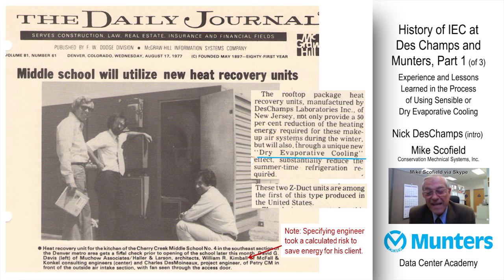So they went ahead and installed the larger tonnage chiller, and lo and behold, the system worked. And we were able, it turns out, to keep that chiller, which happened to be an air-cooled water chiller on the roof, off for a majority of the summer hours. So this system worked, and it worked very well. What we didn't know is what we were inviting downstream in terms of plating out of water hardness, and in the application of aggressive water eating up the heat exchanger, the aluminum, taking away material from the aluminum heat exchanger, which is actually worse than plating if you have aggressive water.